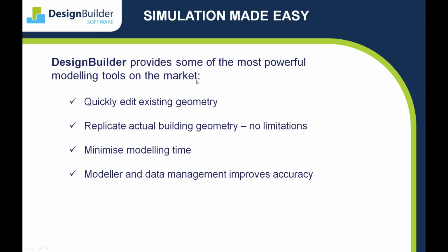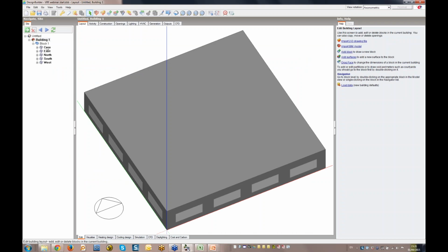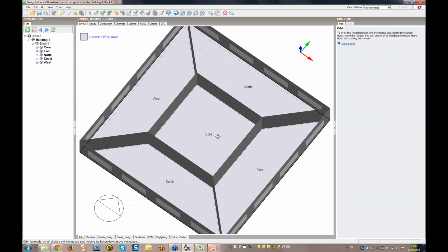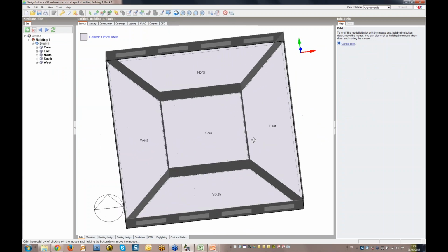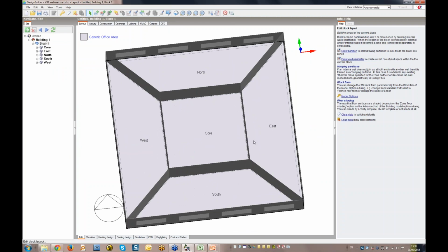In addition to providing powerful geometric modelling tools, DesignBuilder's user-friendly interface and efficient data management system significantly reduces the amount of modelling time required. These qualities help to reduce the risk of modelling mistakes and make you more productive. Here's a very simple model I created earlier with north, east, south, west and core zones. The geometry will result in year-round cooling load in the core zone, but during colder periods we'll get good conditions for VRF heat recovery, which you'll see in our results later. I'll leave most of the model data at default settings and focus only on the HVAC related data today.